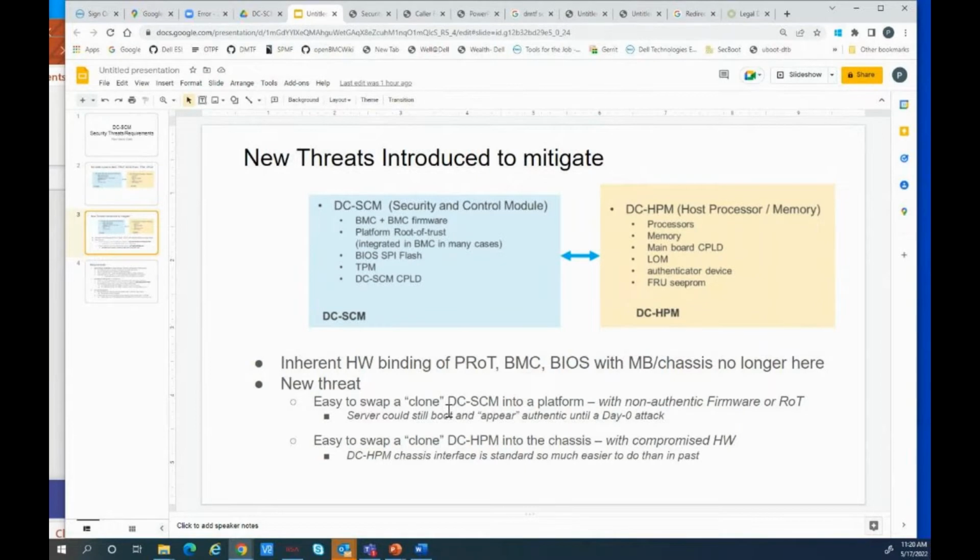We actually had extensive debate on where this TPM should be. Of course, at the end of the day, we decided that it should be on the SCM. Well, it is defined as optional, right? It doesn't say it should be on the DC-SCM. But if you're single node, you should have one. But then we ran out of interfaces, and because this thing also supports dual node, you can independently boot two domains via this interface. I'm not sure if that was obvious to anyone because it seems to be a niche, but it is supported there.